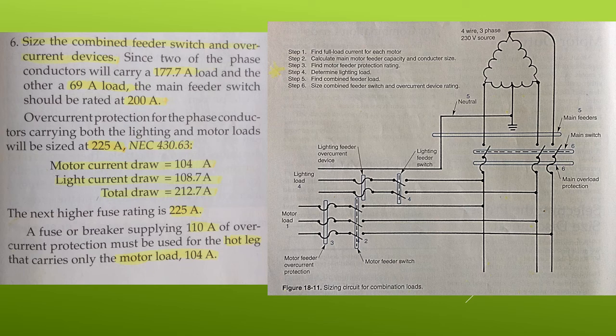Finally, Step 6, size the combined feeder switch and overcurrent devices. Since two of the phase conductors will carry a 177.7 amp load and the other a 69 amp load, the main feeder switch should be rated at 200 amps.